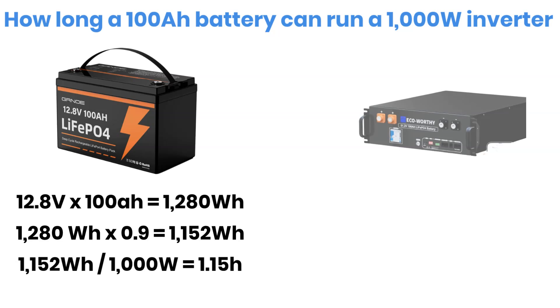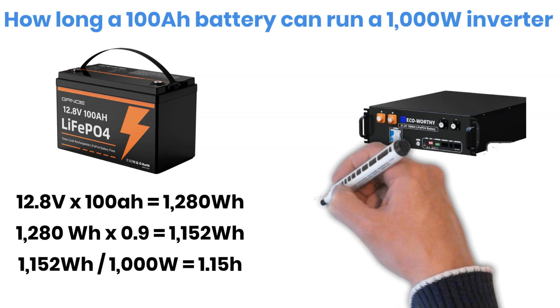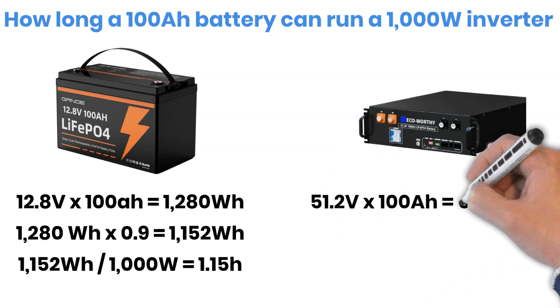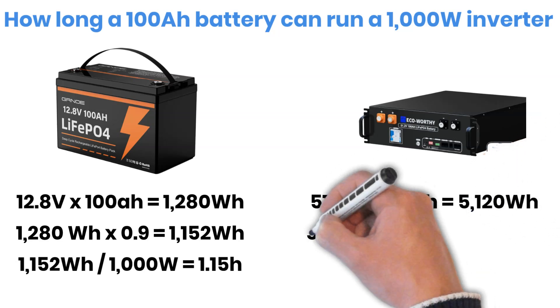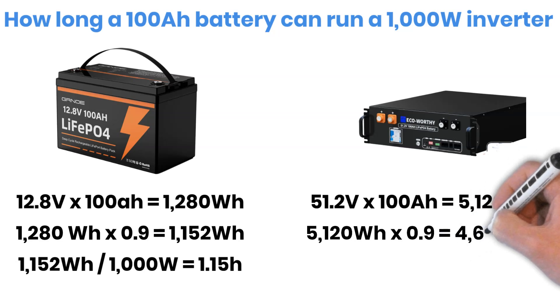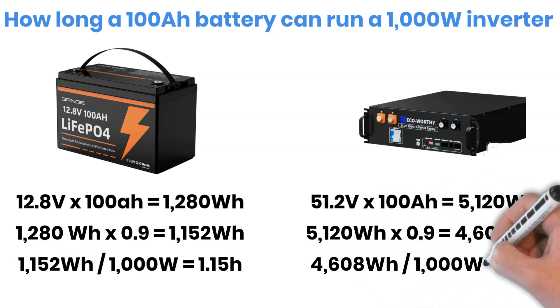For a 48 volt, 100 amp hour server battery, total energy is about 5,120 watt hours. After efficiency losses, you'll have roughly 4,608 watt hours available. So with a 1,000 watt load, it can run for around 4.6 hours or about 4 hours and 36 minutes.